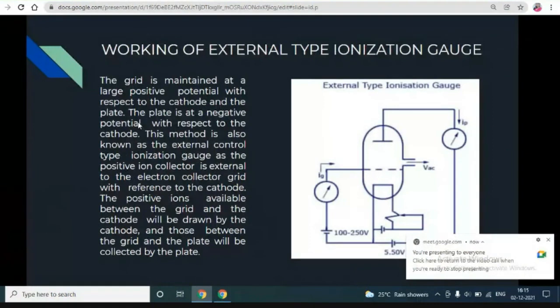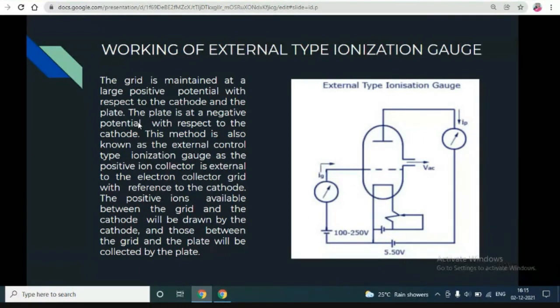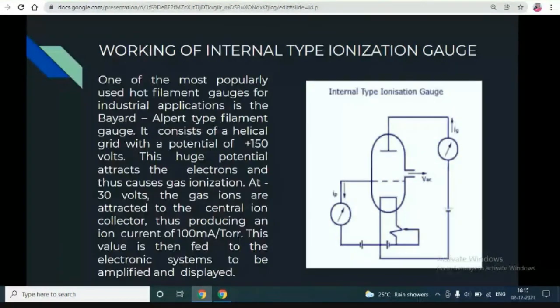The grid is maintained at a large positive potential with respect to the cathode and the plate. The plate is at a negative potential with respect to the cathode. This method is also known as the external control type of ionization gauge, as the positive ion collector is external to the electron collector grid with reference to the cathode. The positive ions between the grid and the cathode will be drawn by the cathode, and those between the grid and the plate will be collected by the plate. This is the working of the external type ionization gauge.